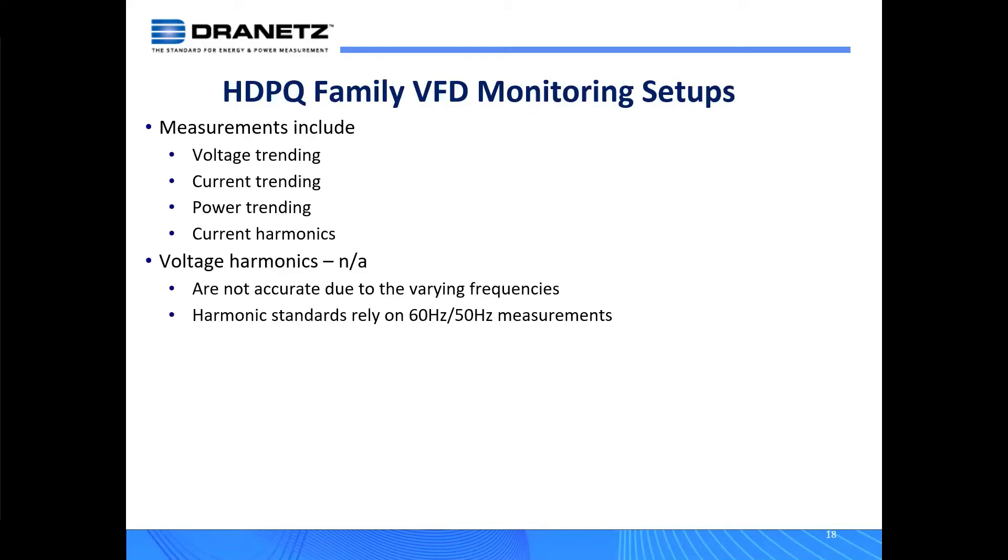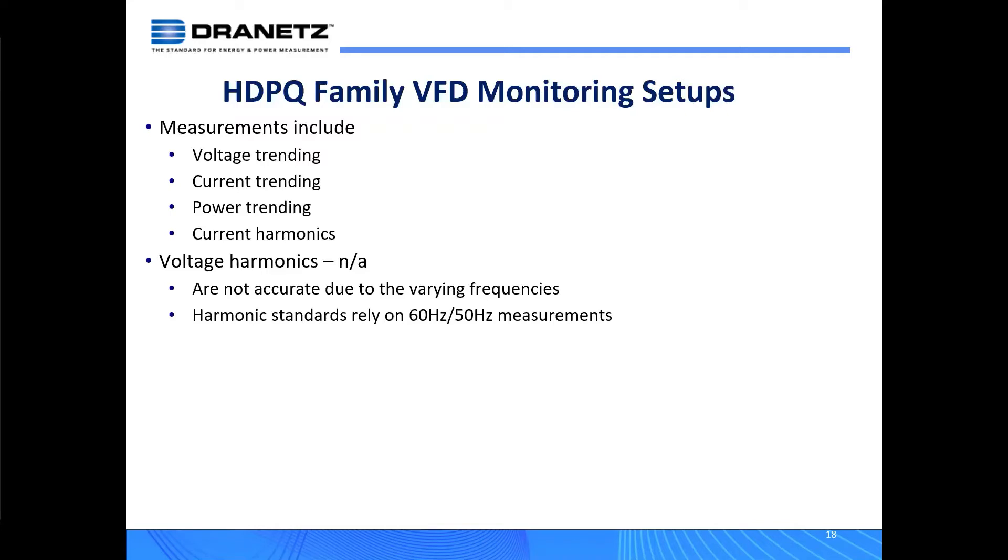Those standards are locked into that type of scenario. However, when you're measuring the output of a VFD, we don't have that scenario, certainly for voltage because of that pulse width modulation. So the voltage harmonics are not available as they would be normally. The current harmonics should be perfectly fine because that's still a 50 or 60 hertz waveform. So as a rule of thumb, you get everything, but the voltage harmonics are not available to you. That's just inherent to the way a VFD works.